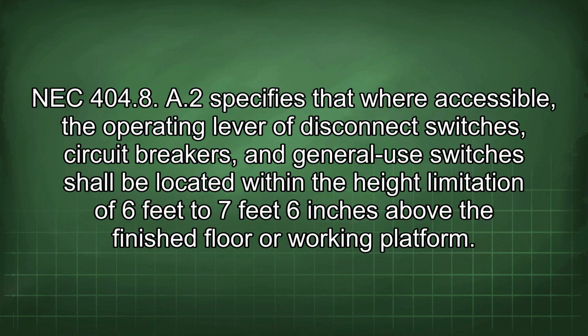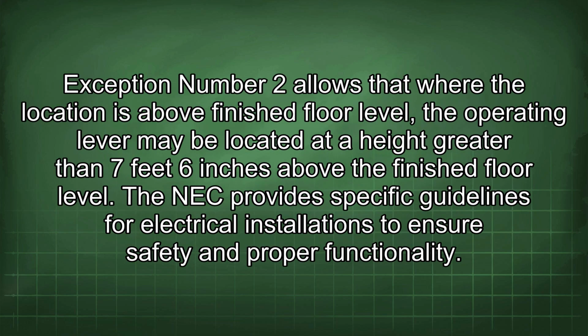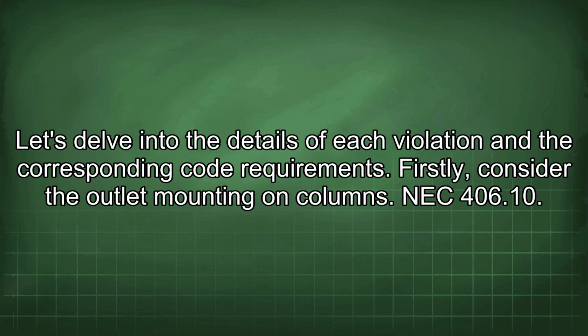NEC 404.8.A2 specifies that where accessible, the operating lever of disconnect switches, circuit breakers, and general use switches shall be located within the height limitation of 6 feet to 7 feet 6 inches above the finished floor or working platform. Exception number 2 allows that where the location is above finished floor level, the operating lever may be located at a height greater than 7 feet 6 inches above the finished floor level. The NEC provides specific guidelines for electrical installations to ensure safety and proper functionality. Let's delve into the details of each violation and the corresponding code requirements.